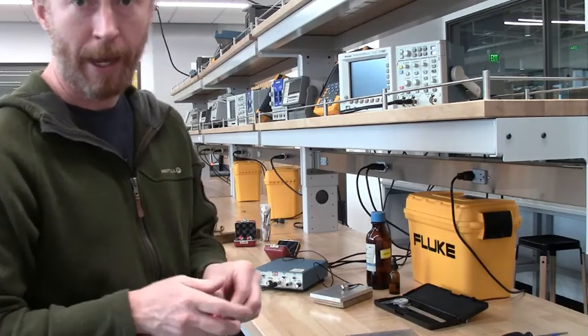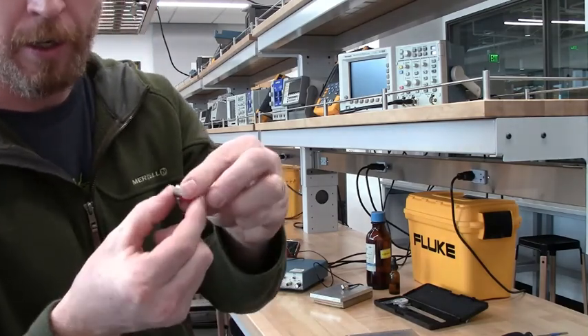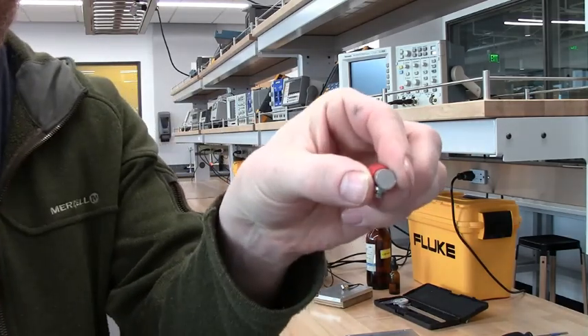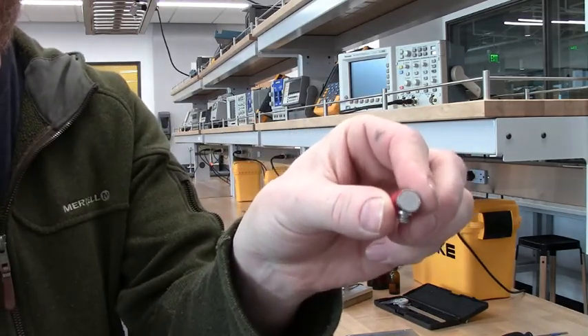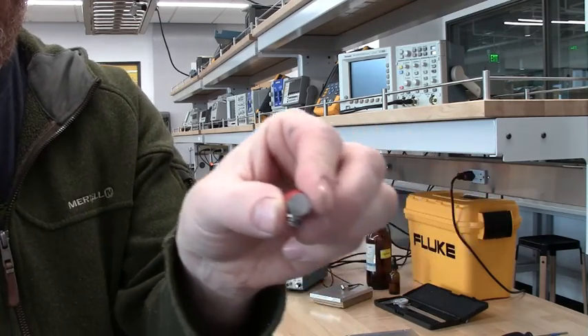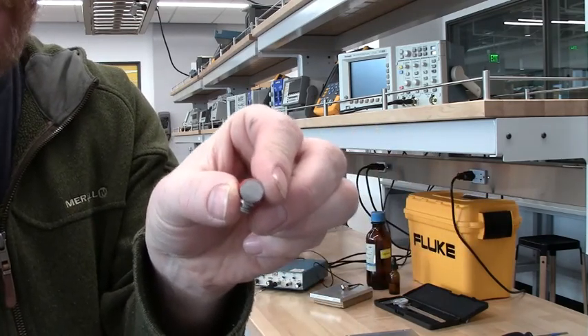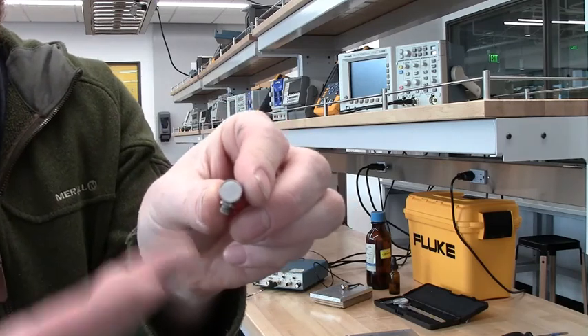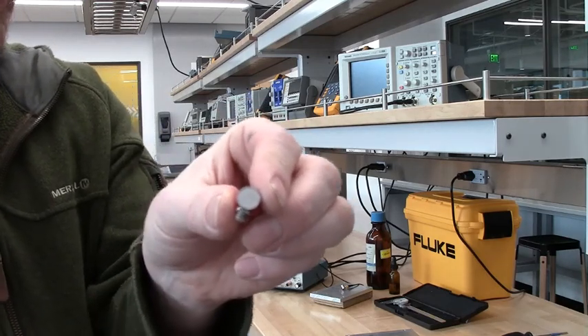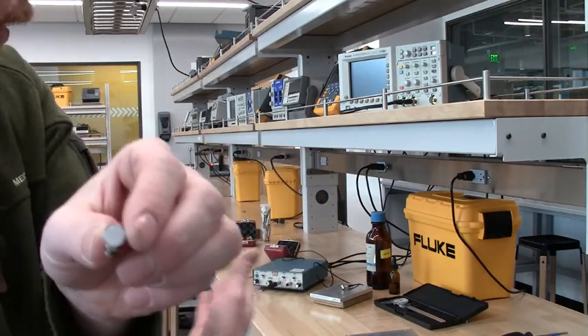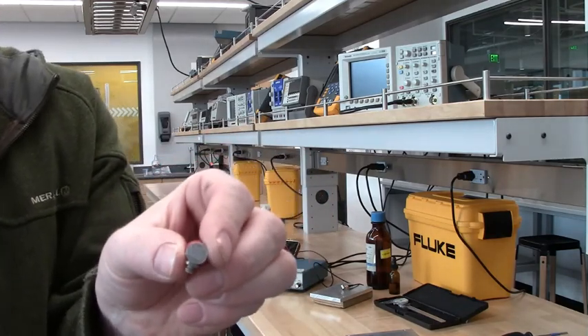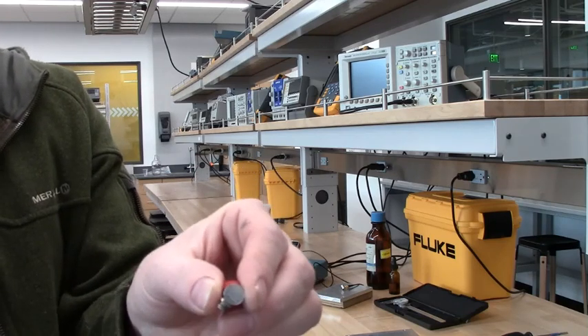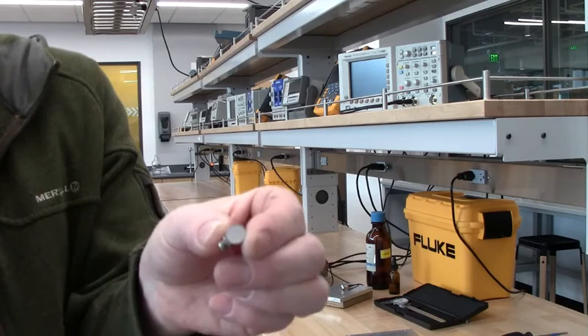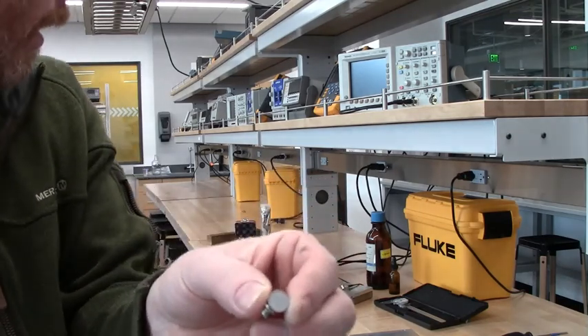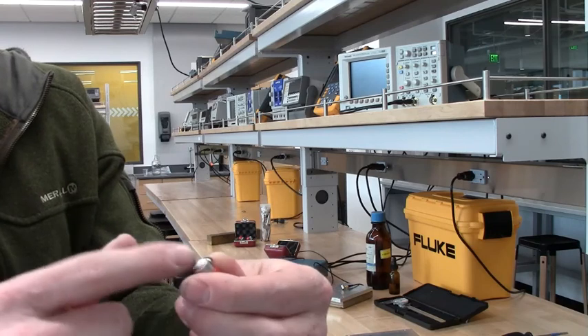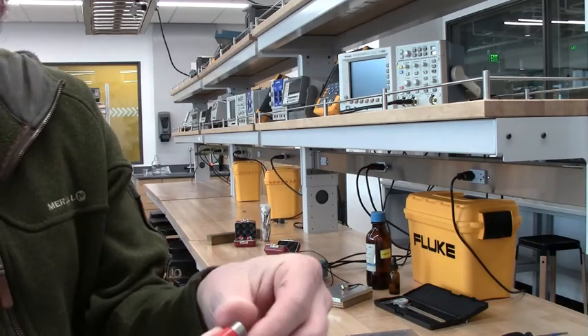Since I'm over here and I have one in my hand, I'll show you that transducer. So this is what it looks like. You might not be able to see this. There's a 10 and a 0.25 written on there. The 10 would stand for 10 megahertz. That would be a higher frequency transducer. That would be better for these smaller samples in terms of the depth. Say 1 inch might be a good rule of thumb. If it's less than 1 inch, this would be good for that. The 0.25 is the 0.25 inch diameter of this transducer.